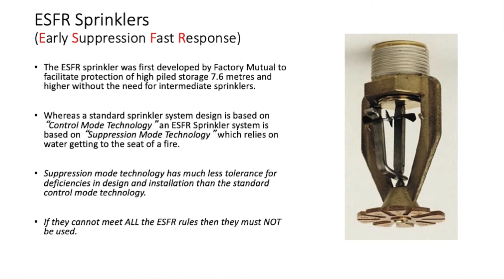ESFR is suppression mode technology. Now what that basically does is extinguish the fire. It works different. So suppression mode technology has much less tolerance, okay, for the design. So the building has to be designed along with the sprinklers to make sure that the ESFR systems work properly. If you can't meet them, you shouldn't be using the ESFR. Unlike standard sprinklers, right, standard sprinkler systems are designed for a density over an area. ESFR systems are designed for amount of heads working. So ESFR systems are designed based on 12 heads in operation.